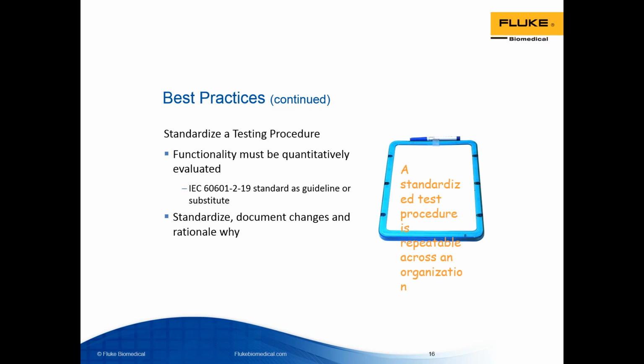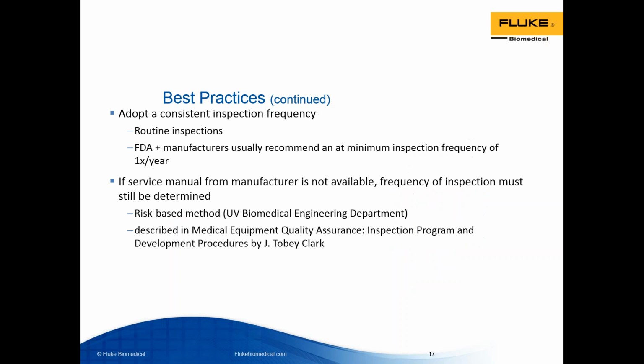If the service manual and the inspection procedure from the manufacturer is not available, it's still the responsibility of the medical facility to choose and standardize on a test procedure. It's important that the infant incubator functionality be evaluated quantitatively by comparing it to the applicable medical device standard or the manufacturer's specifications. If the manufacturer's specifications aren't known, again, the IEC 60601-2-19 standard is a great place to start and a more than reasonable substitute. Once the inspection criteria have been agreed, no changes should be made without a rationale statement describing why a change was required, what the change is, and then how this change was validated.